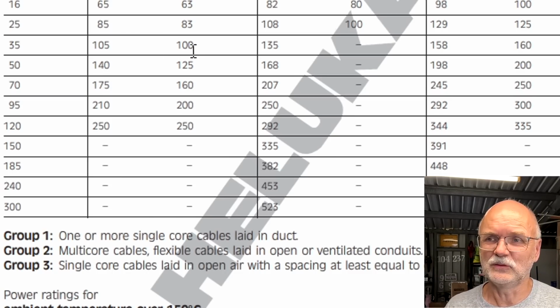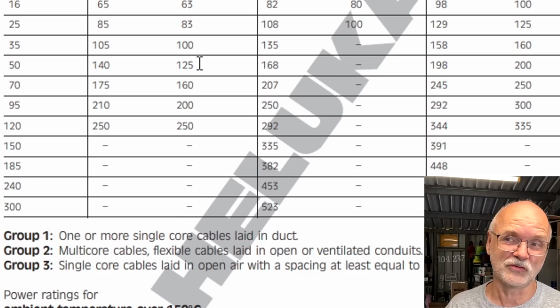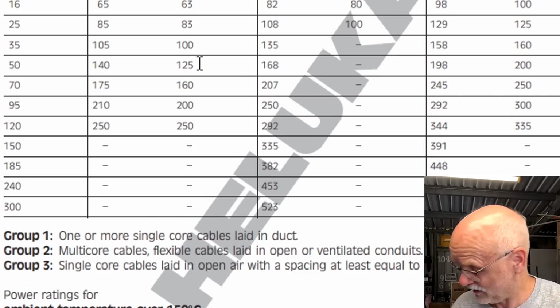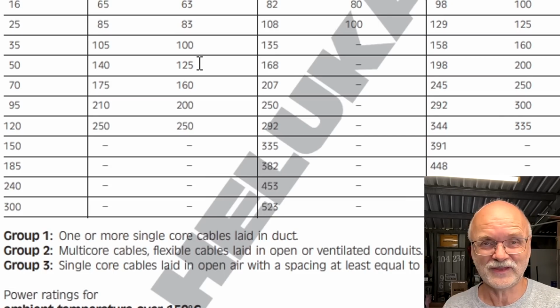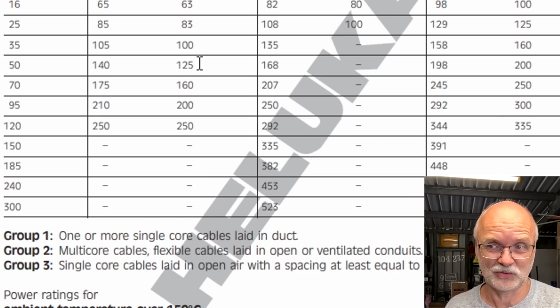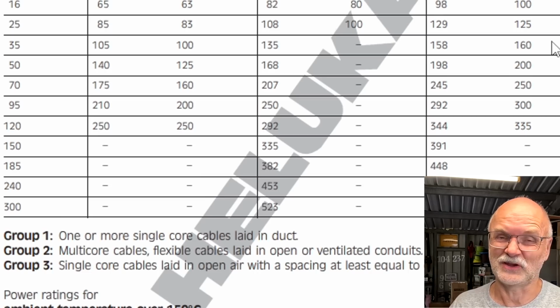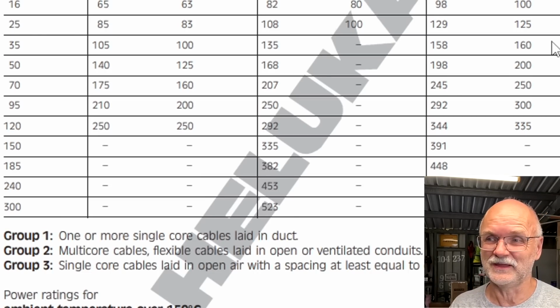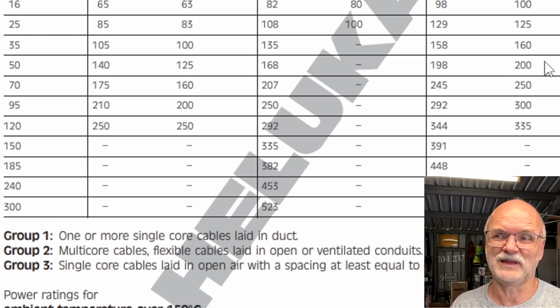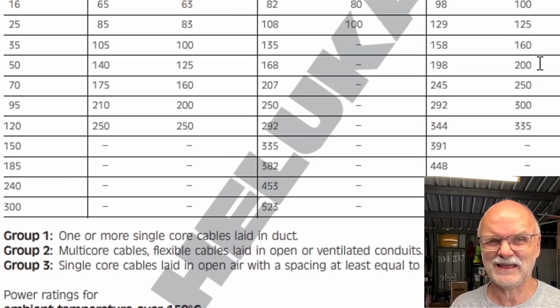We can use a fuse of 100 to 125 amps for this 35 square millimeter cable, but we have a 250 amp breaker in this circuit. And even if we are very, very generous and go to group number 3 and have a look at 50 square millimeter, which we don't have, it is recommended to have a 200 amp fuse for these silicone cables, not a 250. So the cables are still a bit too thin.